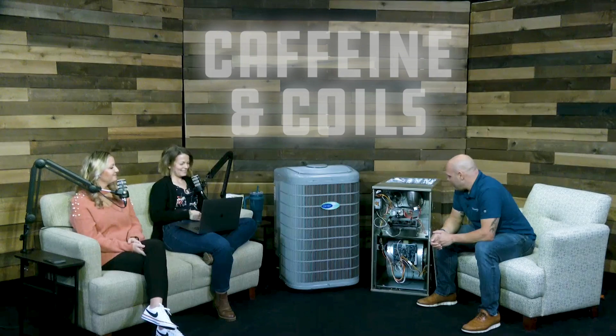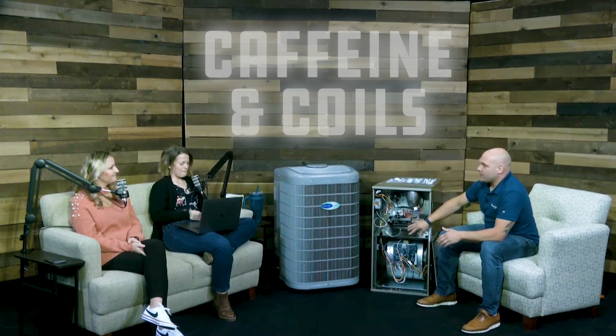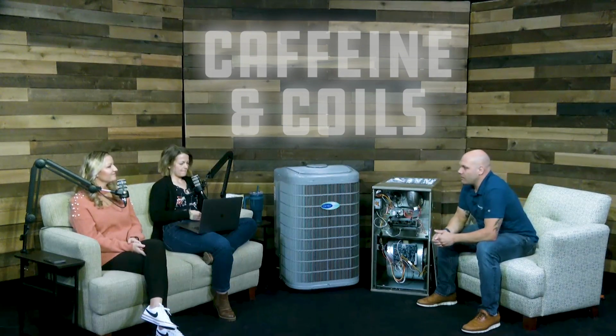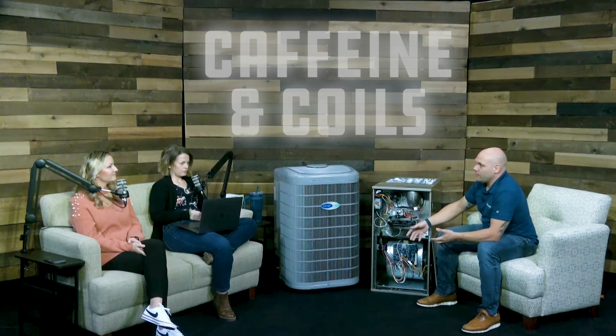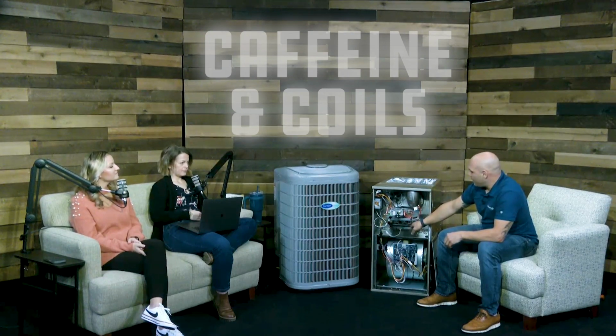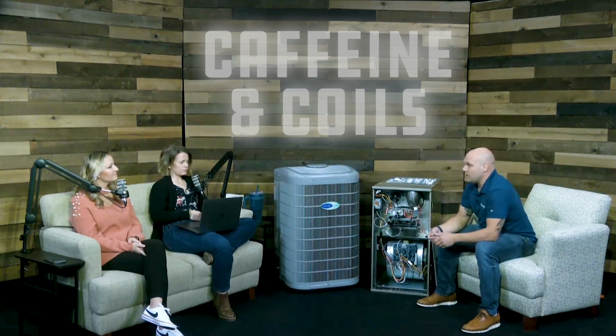A lot of people have service contracts, and within a service contract there are certain things that we look for as technicians to help prevent error codes in the future. I mentioned the flame proving switch. That is a common part that will get dirty. It may not be bad, it's just dirty.